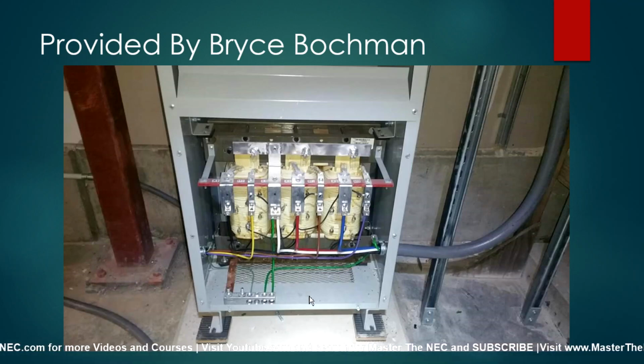It cannot be located over any of the venting. Okay. This is where convection venting air comes through, comes out the top, heat rises, pulls in air, and it kind of keeps this dry-type transformer cool. Okay. It does look like he has a system bonding jumper installed. I don't see any grounding electrode conductors, so I'm assuming that it's just incomplete at this time. And so the cover's off of it, so it's probably just not energized at this time. So they still got a little work to do. That's okay. You got a lug left to take care of it.